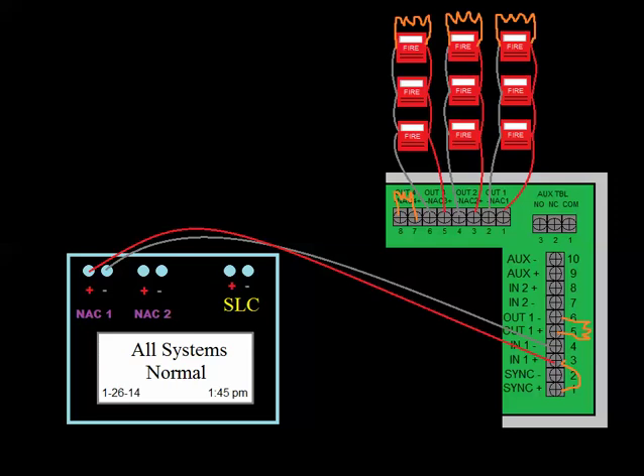And then gray, I'd go 4 to 2, another little jumper here. And all I'm doing is now that's the sync input. So that's the pulse that it's going to get. And now all of these are going to follow that sync that's being triggered from the fire alarm panel.